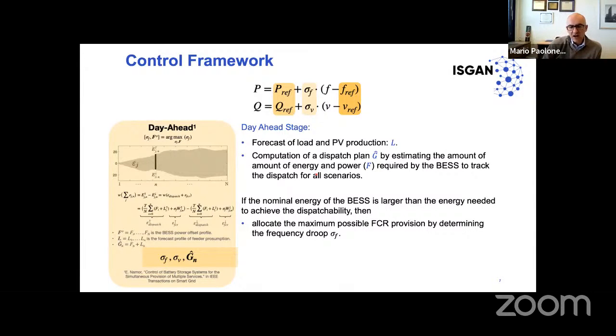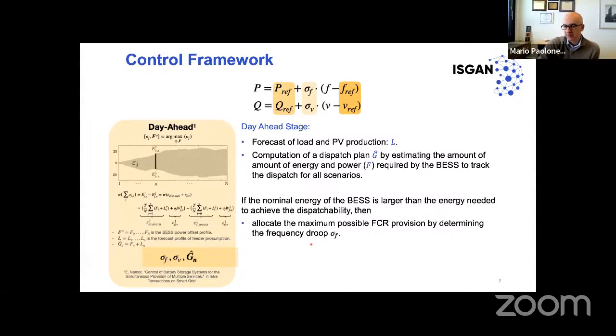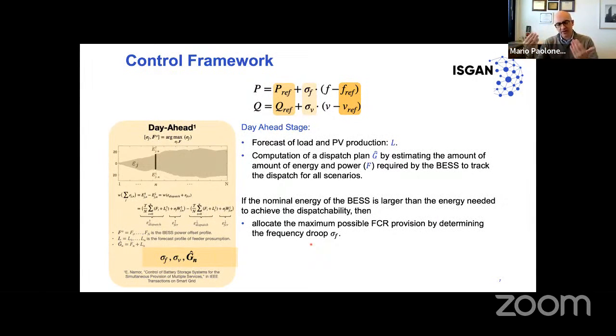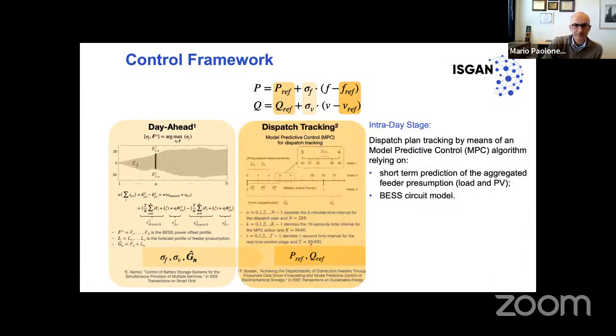Then, if at the end of the day-ahead dispatching exercise you have leftover battery capacity that is not used—and you can compute this day ahead because you run the computation for all possible scenarios—that leftover capacity is used to compute the maximum droop coefficient your battery can provide to the system. This is how we prioritize the services: we first do the dispatch, and then with the leftover capacity, we allocate it for a given droop, that is, regulating energy to the system. You can also invert the two, it's up to the user, but we prefer this hierarchy with dispatching first.